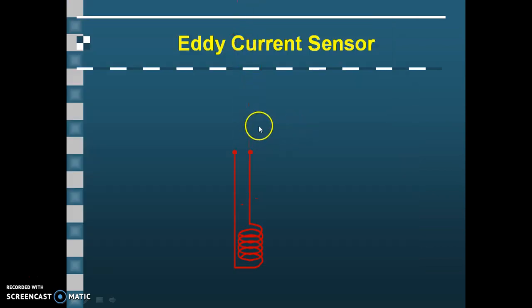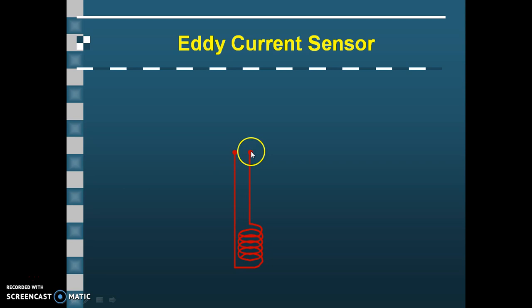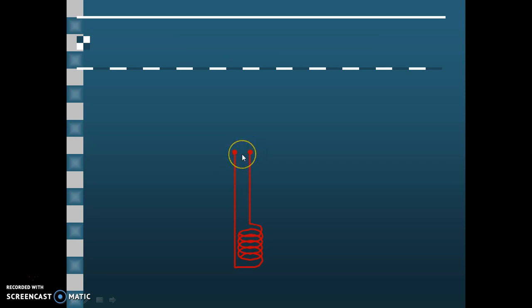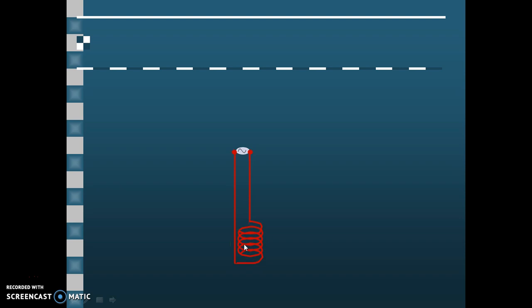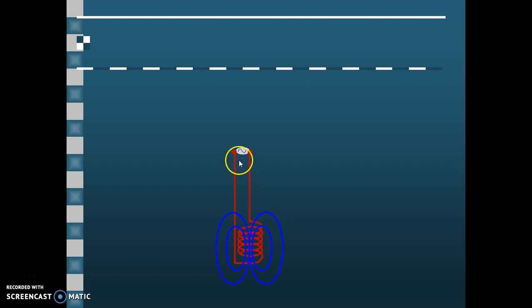The basic principle of the eddy current sensor is: here one coil is there, and across the two probes of the coil we apply an AC current source. As a result, the coil will produce an electromagnetic field across it. These blue circles are showing the generated electromagnetic field due to the alternating current applied at the two probes of the coil.